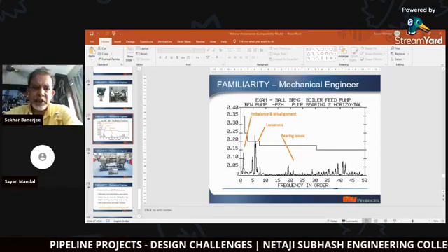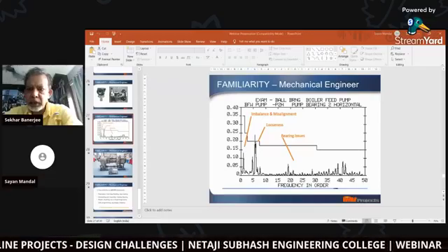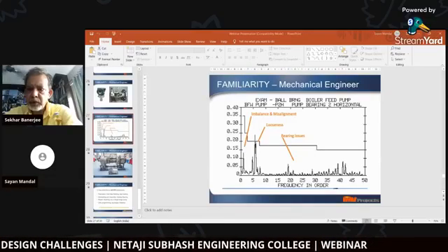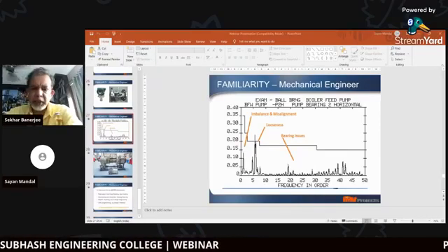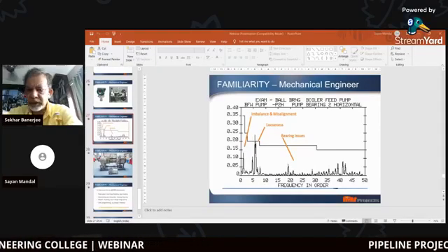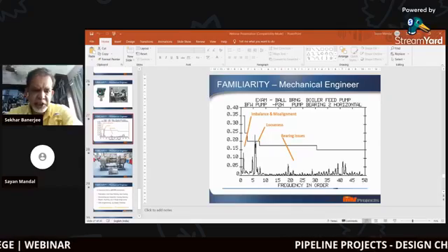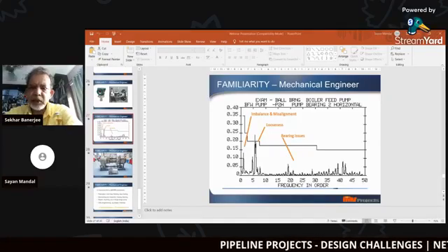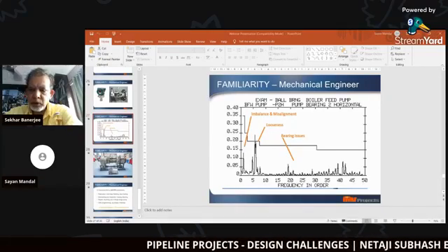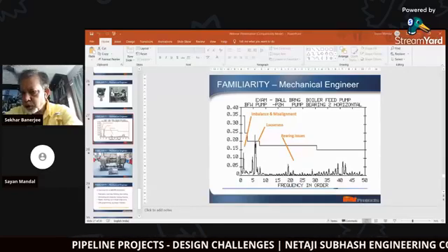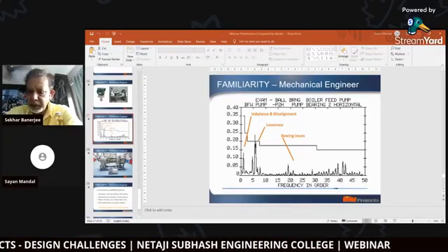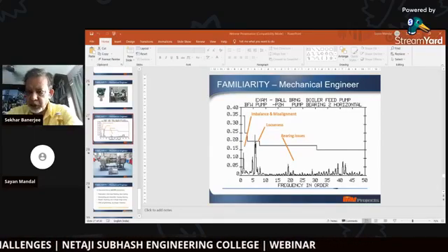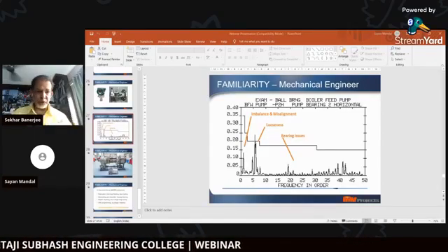We get a high frequency very often in the range of 5 for looseness. And then the bearing issues. Now, a bearing has 7 different balls, right? And there are normally 2 or 3 bearings in a shaft. All the bearings create a little bit of sound. All those sounds come here. Again, if we see a very high pitch here at 20 or 25, you probably think of changing the bearing.